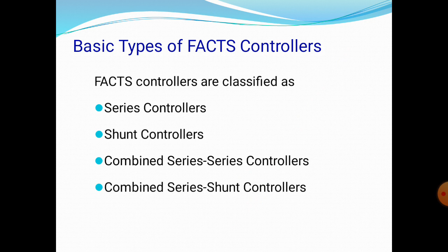First one is series controllers. A series controller could be a variable impedance, that means capacitors and reactors, or power electronics based variable sources of main frequency, synchronous and harmonic frequencies, to serve the desired need. All series controllers inject voltage in series with the line. This is a very important thing about series controllers. All series controllers inject voltages in series with the line, as long as the voltage is in phase quadrature with the line current. So voltage and current are in phase quadrature. A series controller only supplies or consumes variable reactive power.